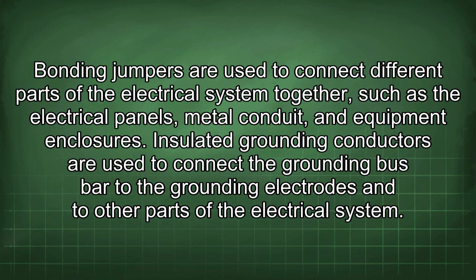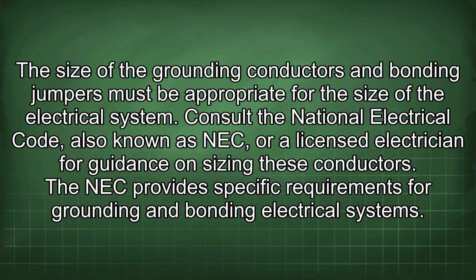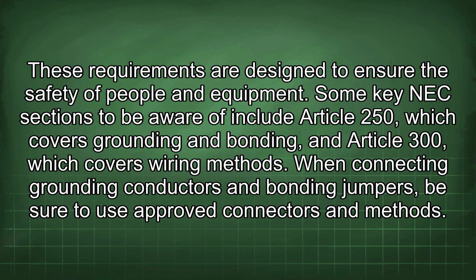Insulated grounding conductors are used to connect the grounding bus bar to the grounding electrodes and to other parts of the electrical system. The size of the grounding conductors and bonding jumpers must be appropriate for the size of the electrical system. Consult the National Electrical Code, also known as NEC, or a licensed electrician for guidance on sizing these conductors. The NEC provides specific requirements for grounding and bonding electrical systems. These requirements are designed to ensure the safety of people and equipment. Some key NEC sections to be aware of include Article 250, which covers grounding and bonding, and Article 300, which covers wiring methods. When connecting grounding conductors and bonding jumpers, be sure to use approved connectors and methods.